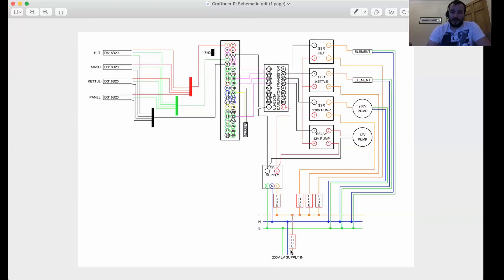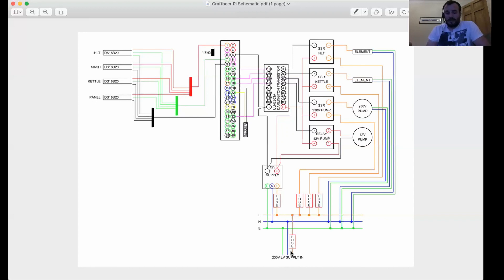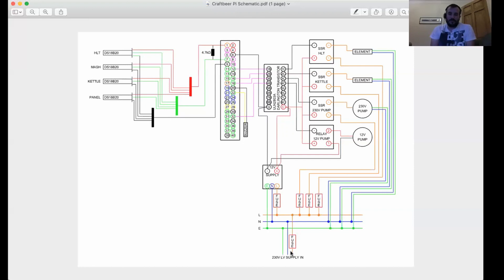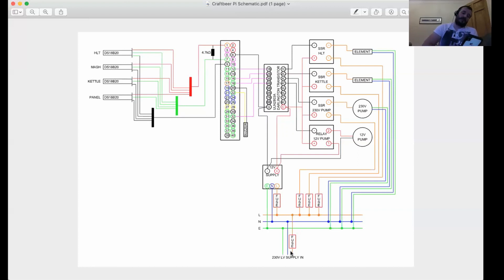If you get bigger setups, you'll probably want to take this directly off a distribution board. Depending on how much power you need, you need to size that up. That's P equals IV, power equals current times voltage. If you've got a five kilowatt setup, the current is P divided by V, which is 230, so 21.7 amps. You're probably going to want a 22 amp breaker would be sufficient.